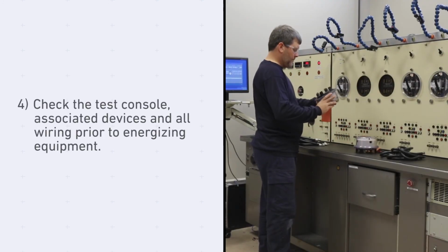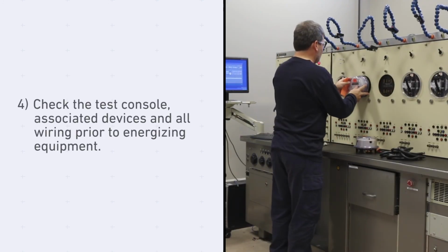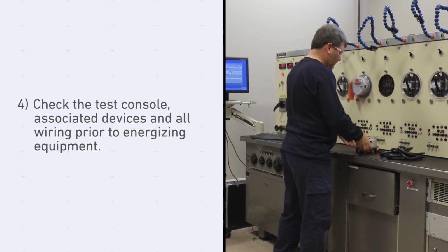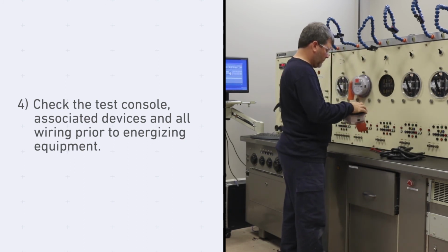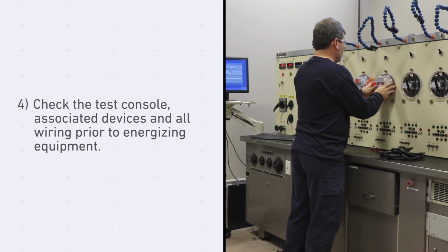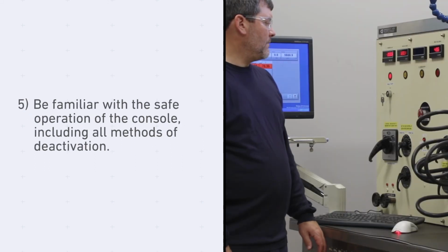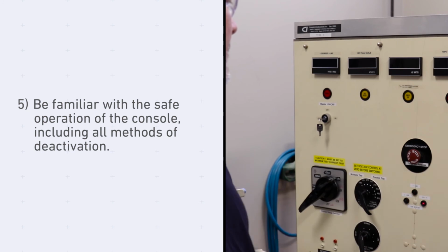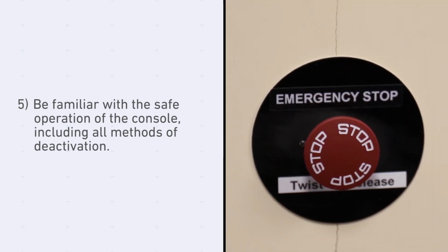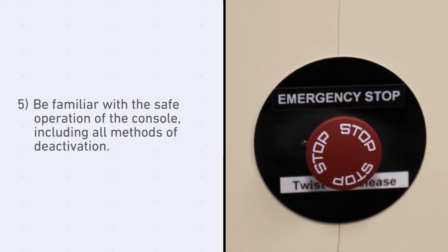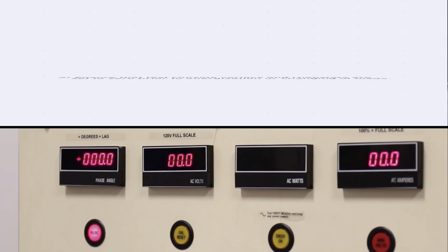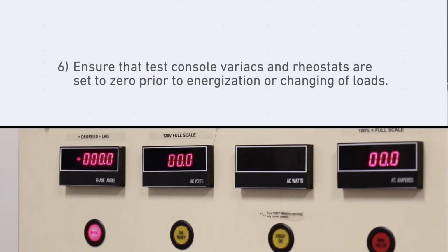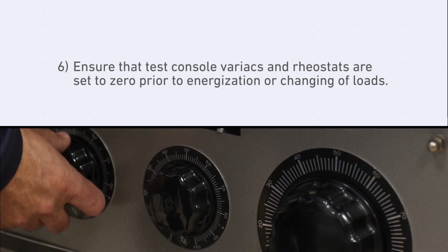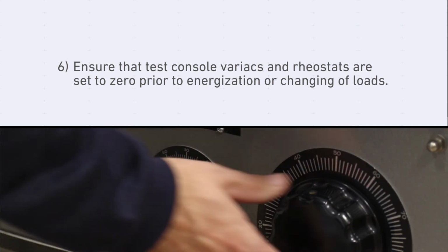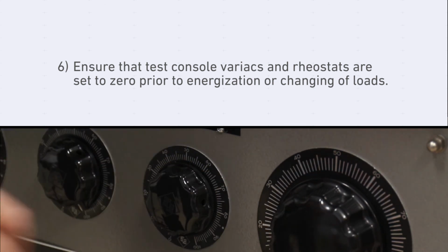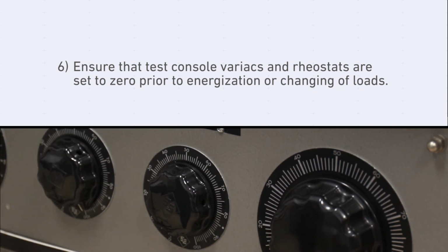4. Qualified employees shall check to see that the test console and associated devices are wired correctly with no loose wire connections prior to energizing the equipment. 5. Qualified employees shall familiarize themselves with safe operation of the test console and know all safe methods of deactivation. 6. Qualified employees shall ensure that variacs and rheostats on the test console are set to 0 prior to energization or changing of loads.